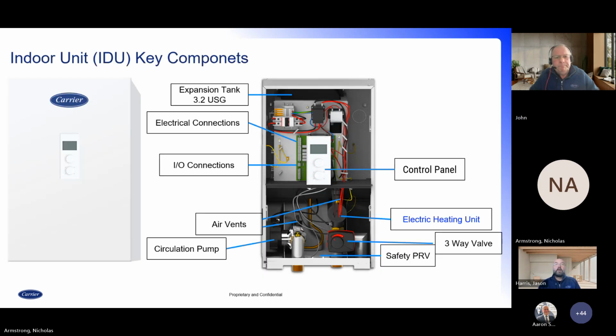Okay, next slide. So here's where the customer is going to interact with their kit, and we refer to this as the indoor unit. As I said, it's the cockpit. There's a lot happening inside this very small box. It's about 18 by 28. It's not a very large box, and inside there we have a pre-charged expansion tank, pre-charged to 14 psig. So it comes right there for you out of the box. All your electrical connections are right on board there. Your IOs are also on board. You have a built-in air vent.